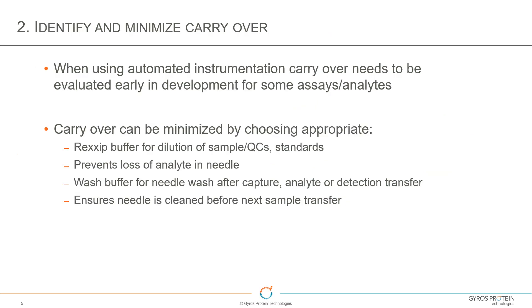When you fully automate an immunoassay, carryover can be an issue because there's needle transfer of samples. It is important that carryover is assessed — in most cases it's not going to be a problem, but we need to look at carryover not just in development, but also any impact when doing more and more runs on the instrument. Carryover can be minimized by choosing the appropriate diluent.